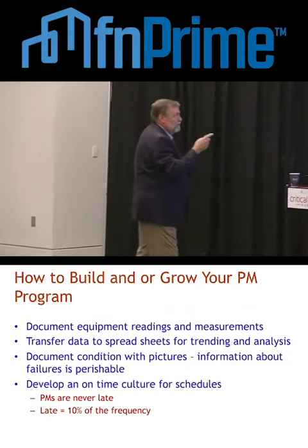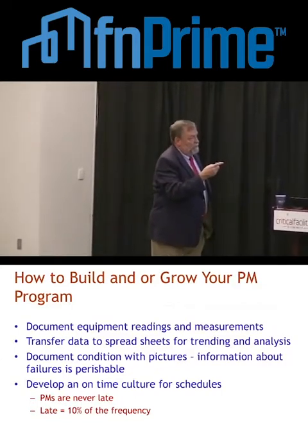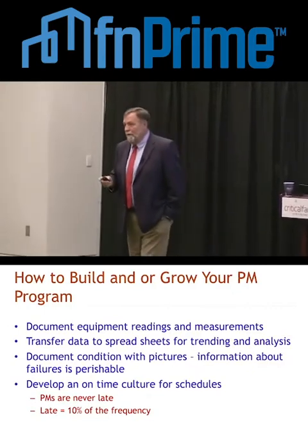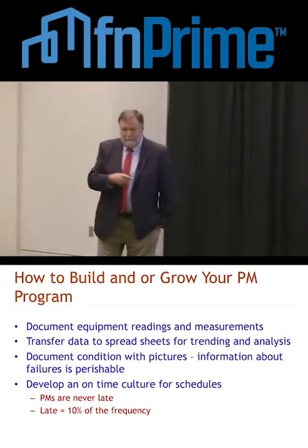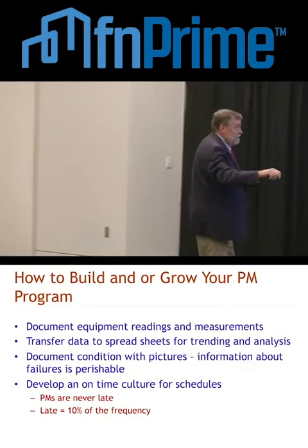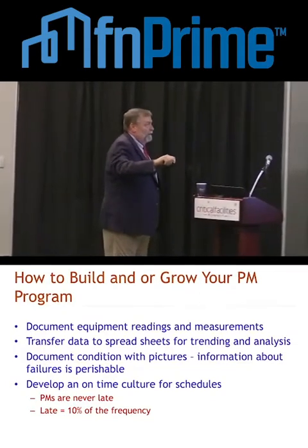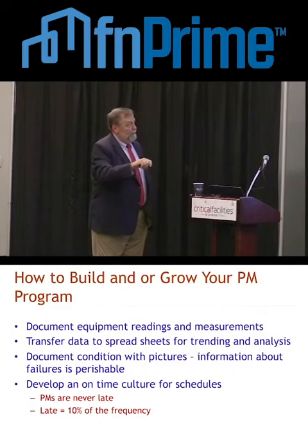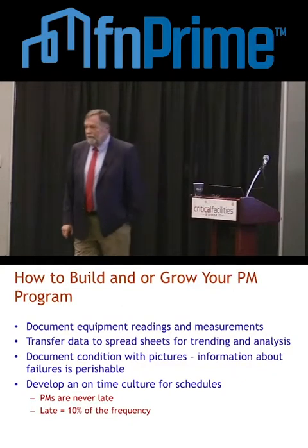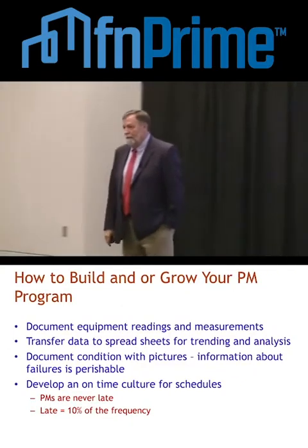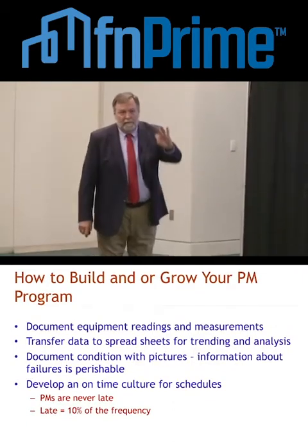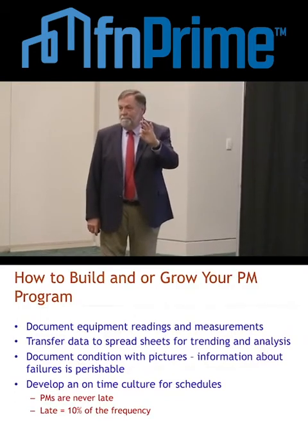And then develop an on-time culture for schedules and PMs. Remember I said never a late PM. That should be your motto. Now here's the definition for what a late PM is. Maybe this will help. You're going to think I'm crazy again. A late PM is 10% of the frequency. So if you have a 30-day PM, you have 3 days to get it done.